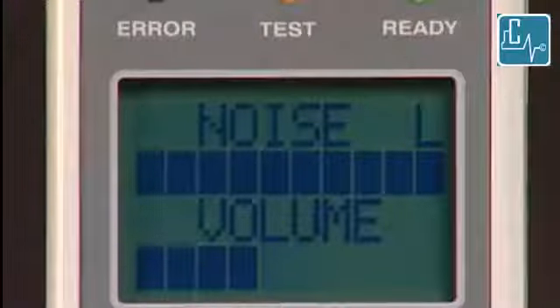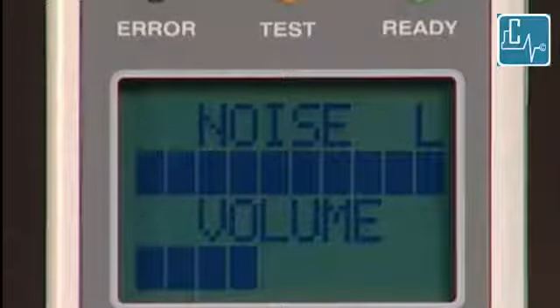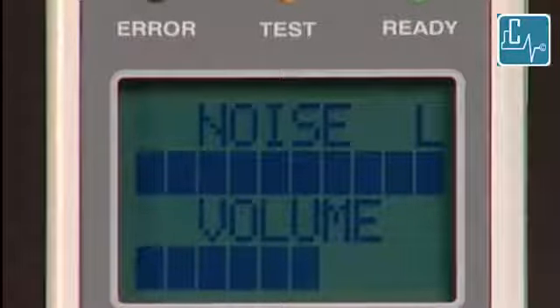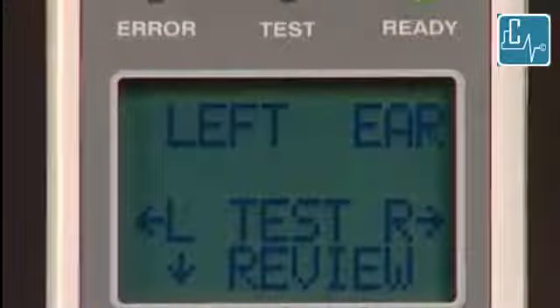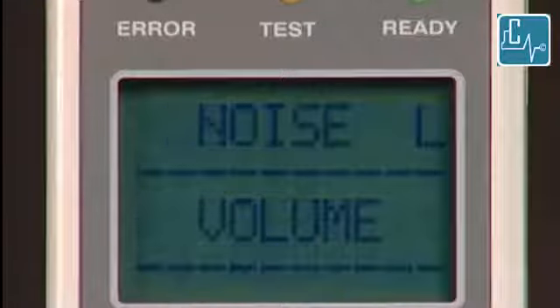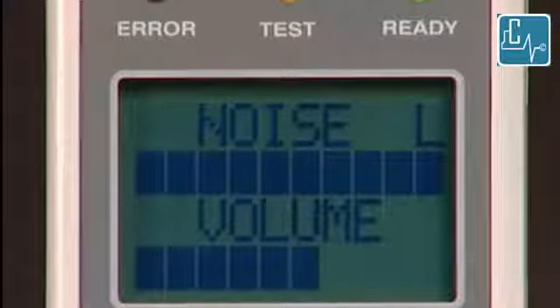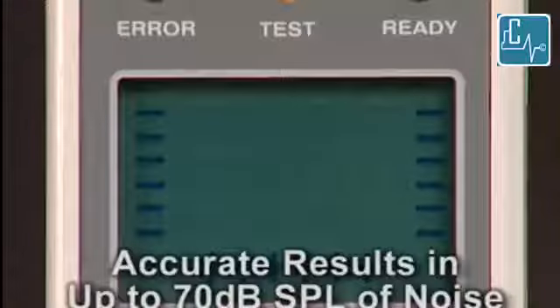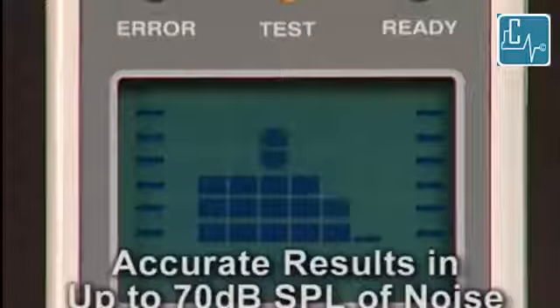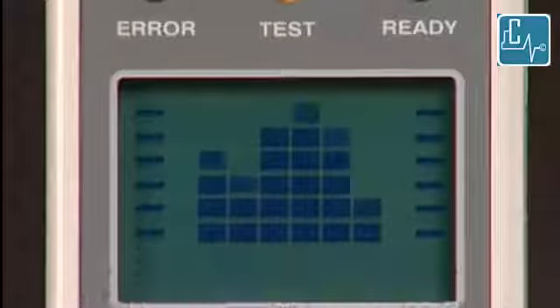If the noise bar will not move to the left, there is either too much noise in the testing environment, the subject being tested is too noisy, or a proper seal has not been obtained. Check for excessive noise and then start again. Please note that while a quiet testing environment is desirable, the ERO.SCAN's artifact rejection allows for accurate test results in up to 70 dB SPL of noise.